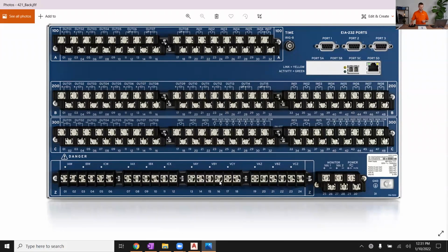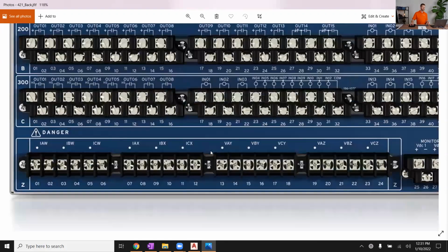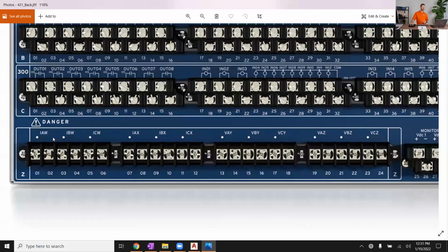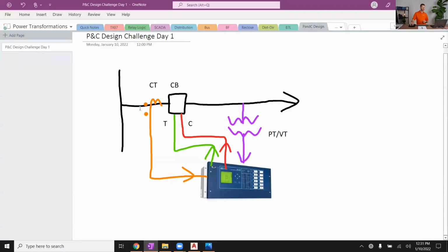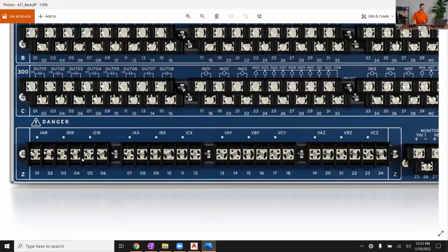And so I want to point out a few things to you. For starters, you see how there's actually two current inputs here on this transmission line relay. There's the W current terminals and the X current terminals. Why do we have two? I drew up this 1 line with a single bus, a single breaker, a single set of 3 CTs, A, B, and C. You could easily wire that CT to this W current terminal and you'd be fine. That'd be sufficient. But there's other situations on the transmission system, usually, not so often the distribution system, where we have 2 breakers at a line terminal.